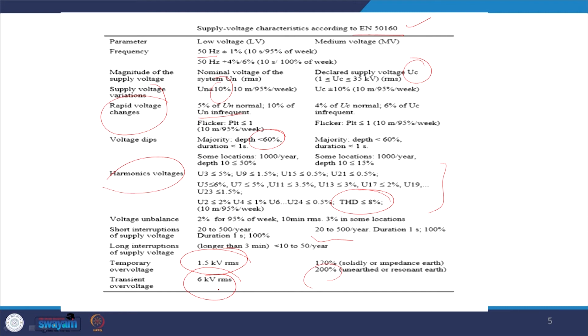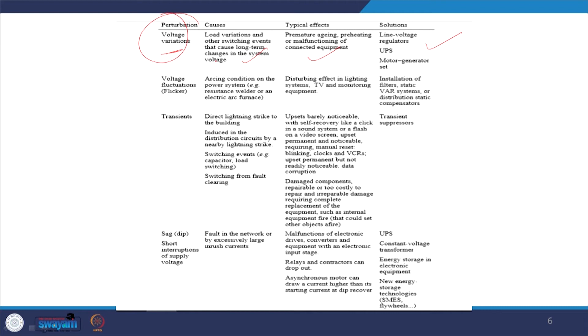So, now what are the implications of it? Let us understand: these are the disturbances, these are the causes, these will be the affected entities, and this is the solution. So, voltage variation. You may have a voltage disturbance, we have seen sag, swell, lot of entities. Mainly it is caused by load variation and other switching events that cause long term change in the system voltage. All of a sudden you overload a big line or you have a sudden fault, and due to that variation of the voltage, there is premature aging of your machines, overheating and malfunctioning of the connected equipments.